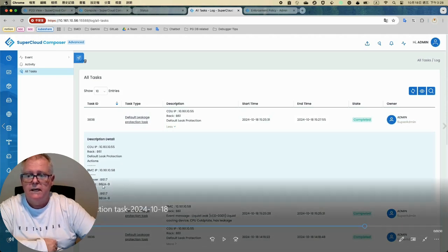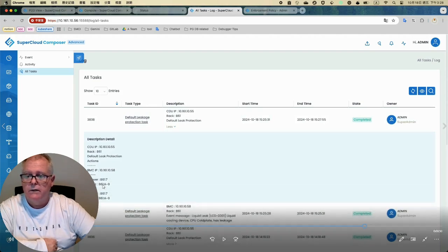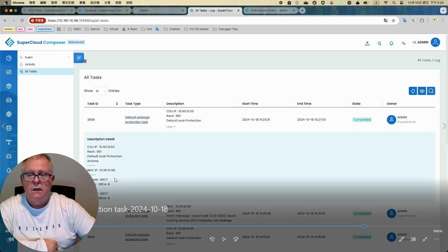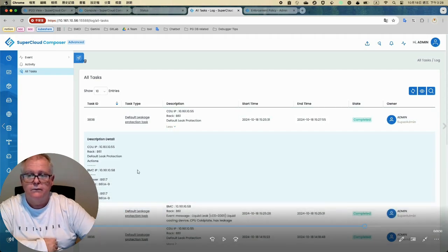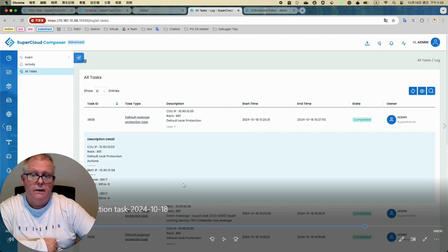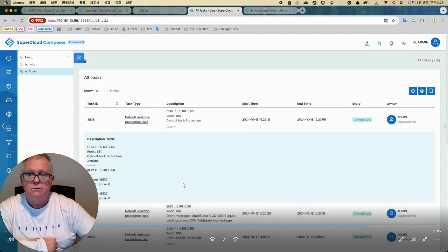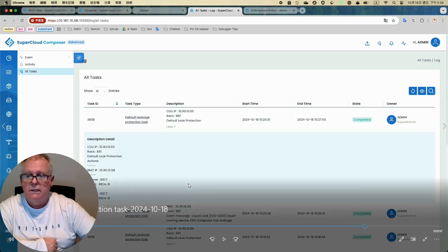The outlet was actually AC powered off, and other metadata would be sent to a Webhook through Redfish subscription services to essentially provide you a precise location of where the leak was through SMTP or perhaps even through SMS. So we laid the foundation also to generate this into a call tracking system such as Salesforce, ServiceNow, Jira, Slack, whatever entity you wanted to push this data to appropriately.